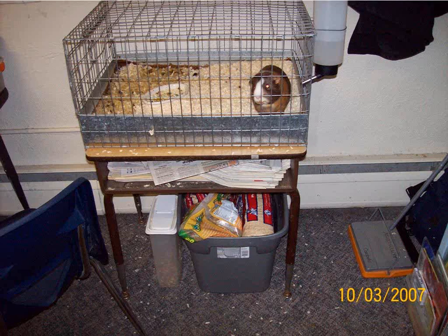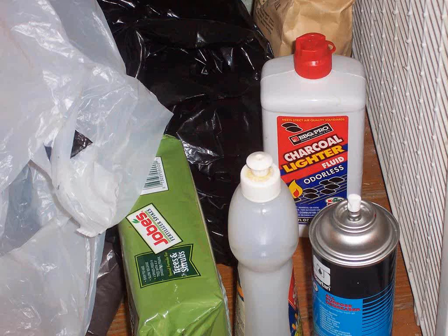And I noticed they have the heating ducts right underneath. Oh my, yes. Right underneath the cage, and the cage looks like it needs a little upkeep. Yeah. Well, that's the problem. I mean, the question is, if you're going to have animals, which we don't recommend, maintaining it, keeping it clean, and then keeping it by the air supply like this. I mean, basically, you're just exposing everybody in the classroom to all of the dander and biological byproducts from a guinea pig. And then, of course, another issue is volatile organic compounds, which come from a variety of cleaning products.